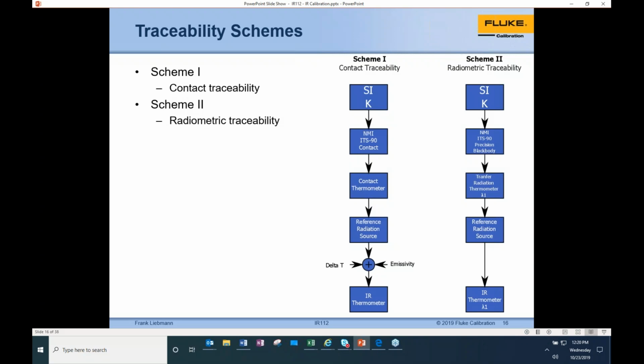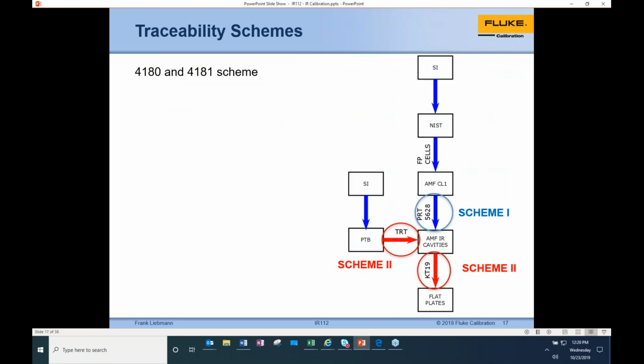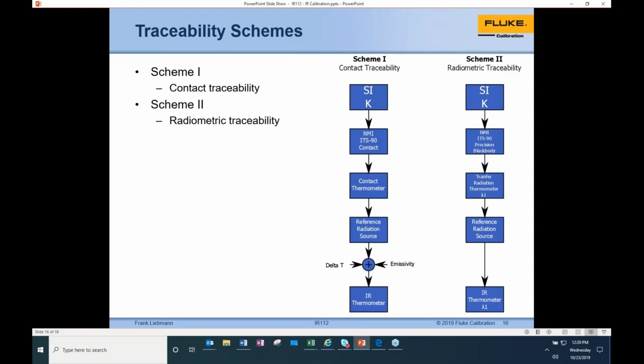In our scheme 1, we've got a little bit more detail on the next slide. Here we go through an example of scheme 1. We would have our fixed point cells calibrated at, say, NIST. This is used in the process for our SPRTs. There are several steps in between each one to calibrate our PRTs, but then we use the PRT to calibrate the IR source. So that's the contact: we're physically touching the pieces of equipment as we go through this unbroken chain.